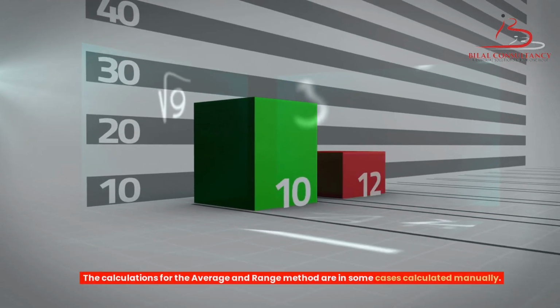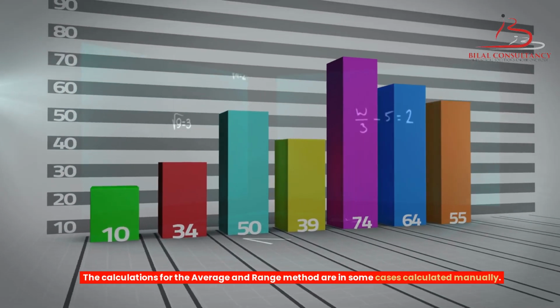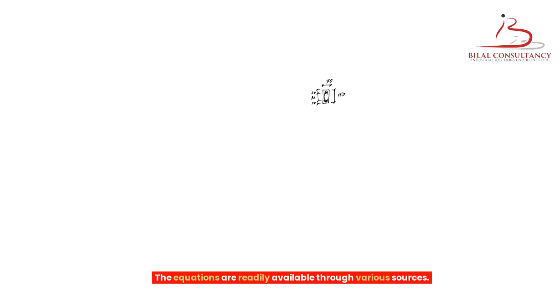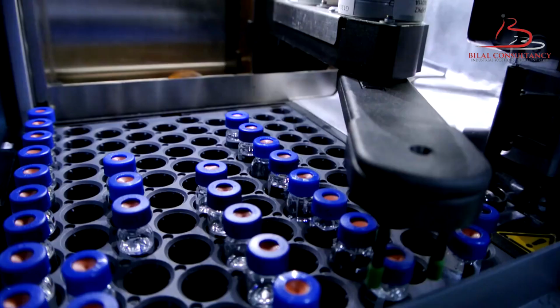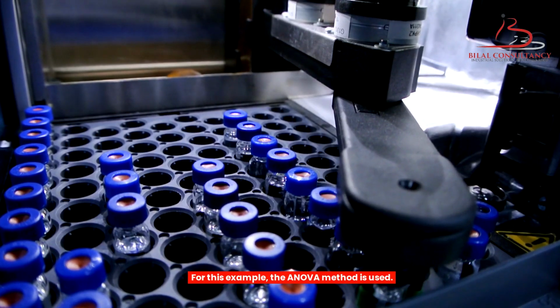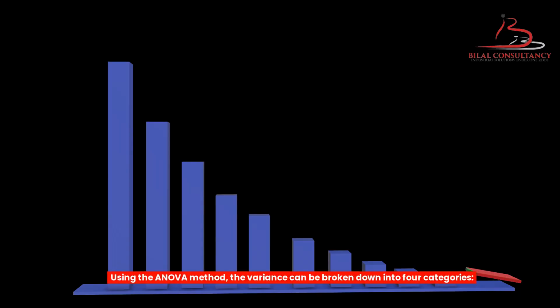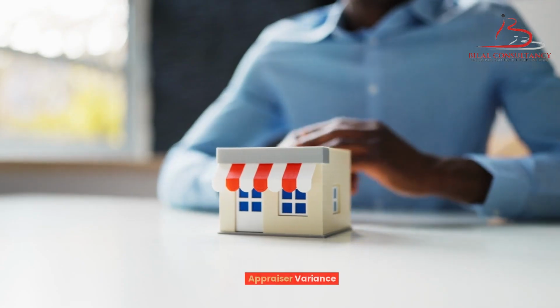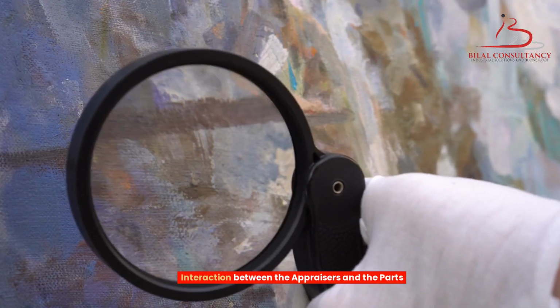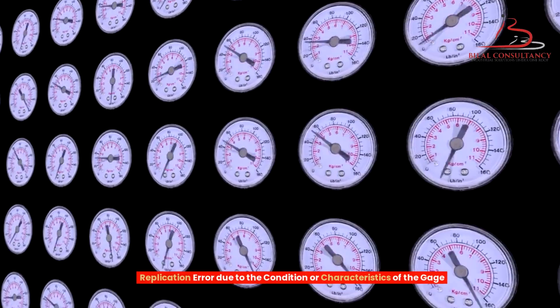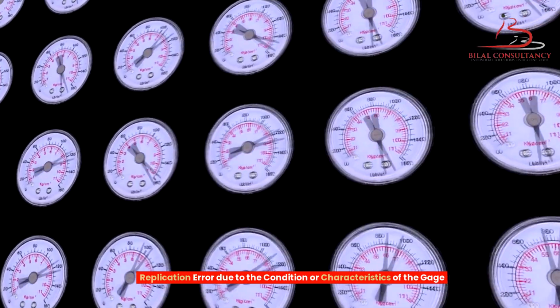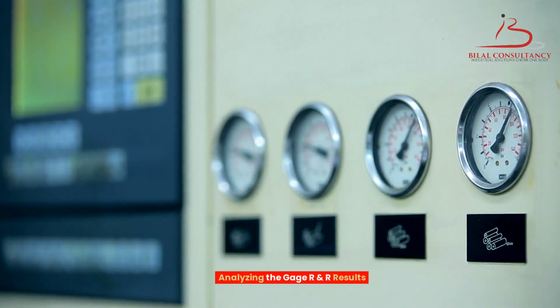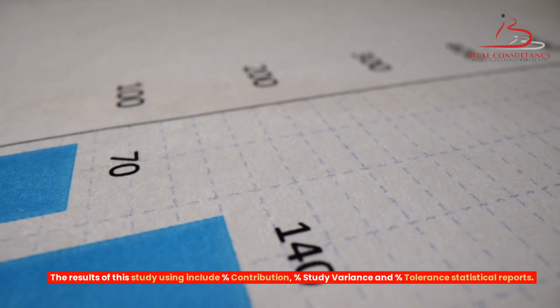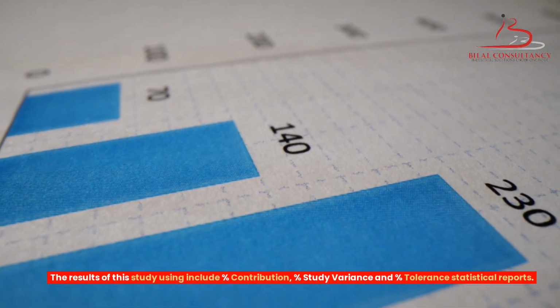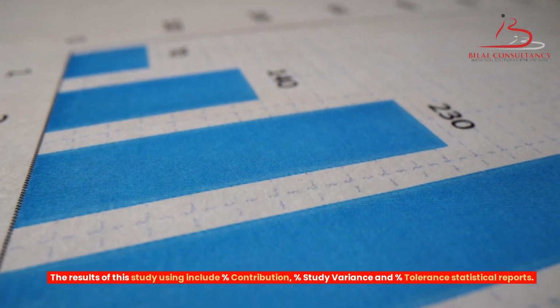Calculations. The calculations for the average and range method are in some cases calculated manually. The equations are readily available through various sources. For this example, the ANOVA method is used. Using the ANOVA method, the variance can be broken down into 4 categories. Part variance, appraiser variance, interaction between the appraisers and the parts, replication error due to the condition or characteristics of the gauge. Analyzing the GageRnR results. The results of this study include percent contribution, percent study variance and percent tolerance statistical reports.